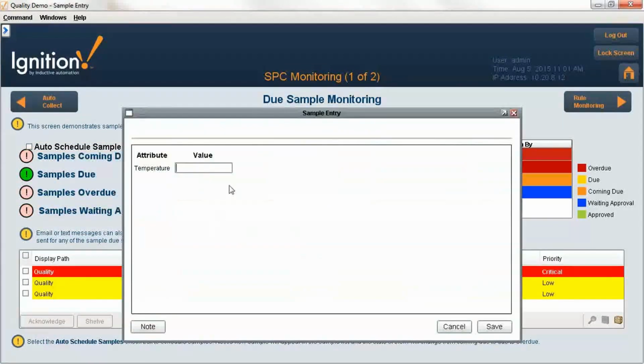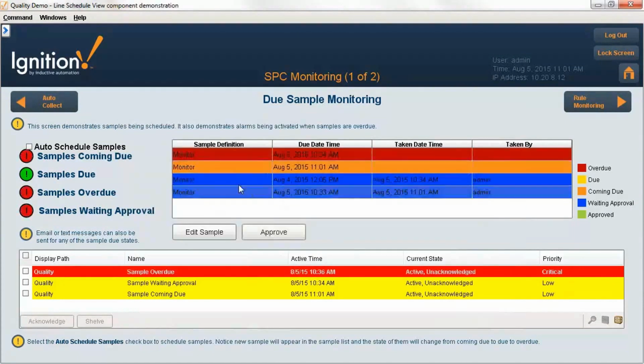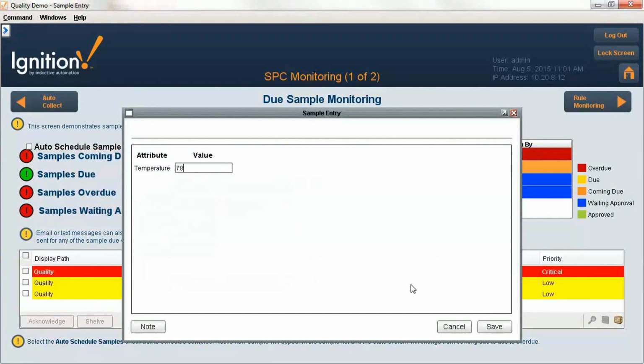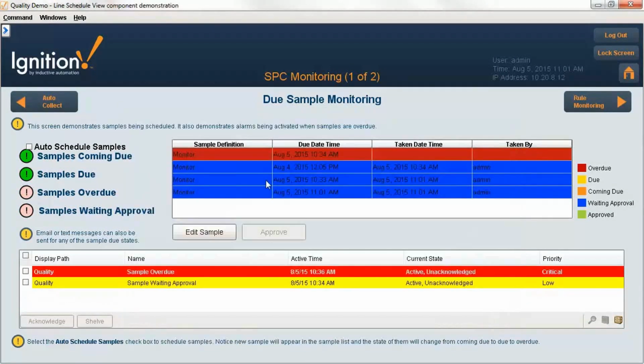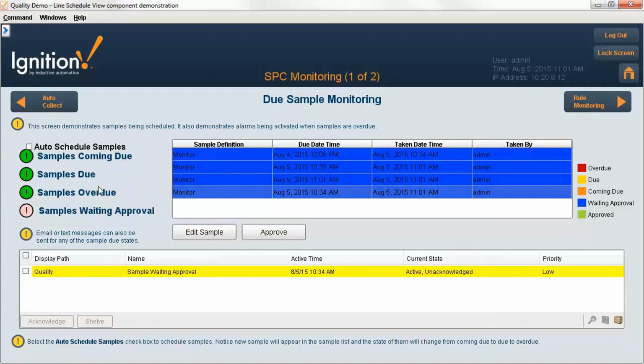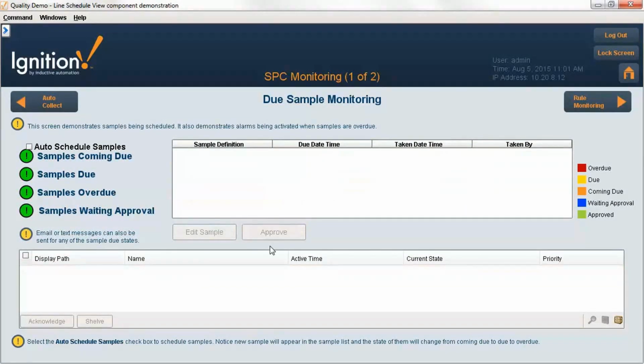As I go in here and edit these samples, I put some values in, and we start clearing some of these different states. If I put the last one in, now I have no samples coming due or overdue, but I do have some waiting for approval. You have the ability to do an automatic or manual approval on your samples. I've elected manual approval, so I'll select all these and approve them. Now they're all approved and all my alarms are cleared. It's a great way to monitor and have accountability for taking these samples in the system.